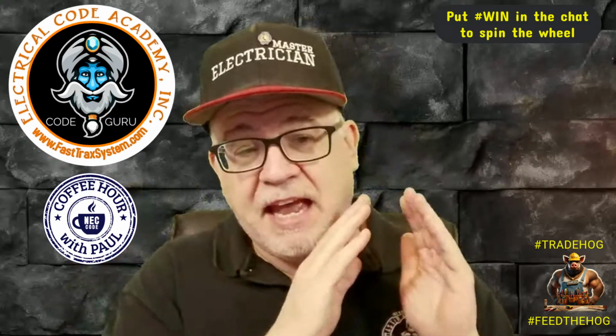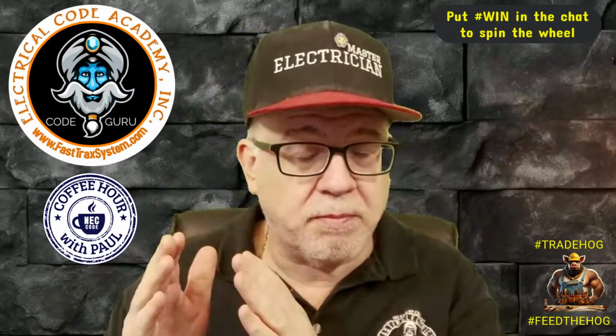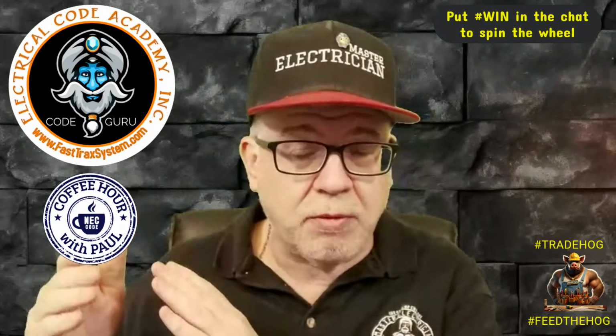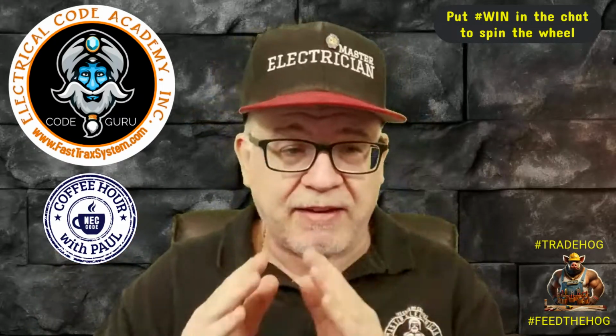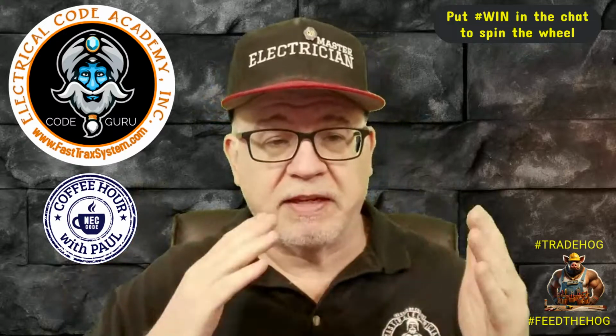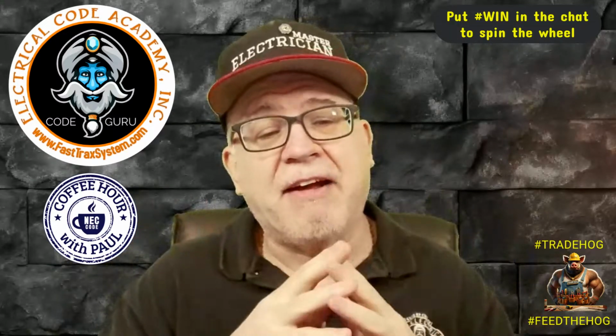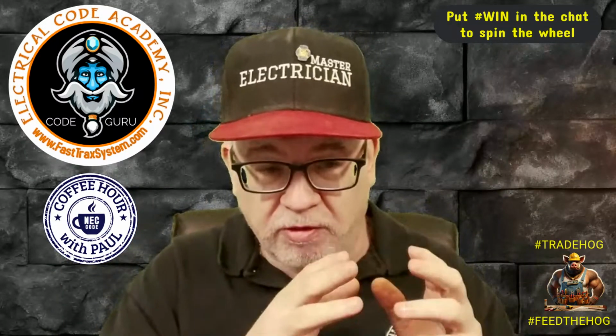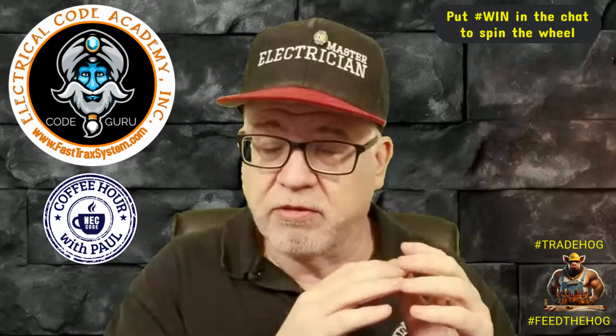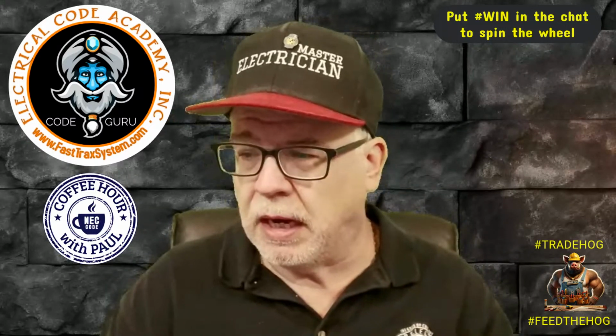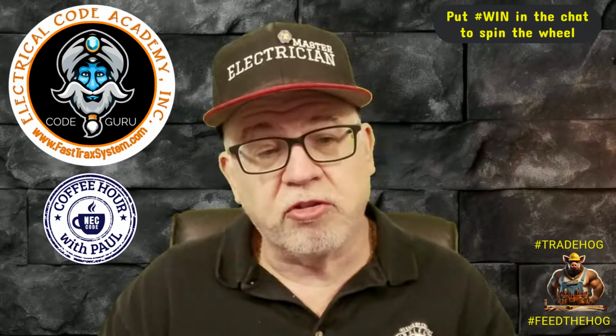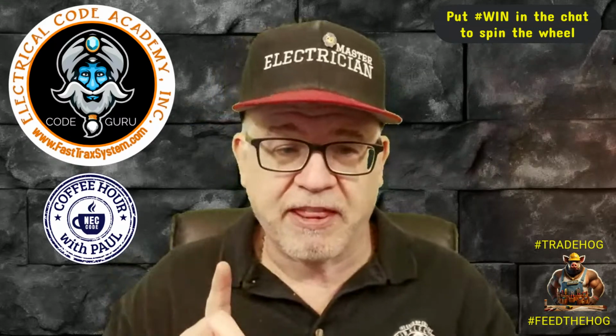Now, could I have the A's be copper and the B's be aluminum and the C's be copper-clad aluminum? Absolutely, as long as the ampacities correspond. Okay, there's going to be a difference in sizes, obviously, but I have to keep the same characteristics per set. Okay, so per phase set. But other than that, I encourage you to go look at 310.10(G) for that situation.